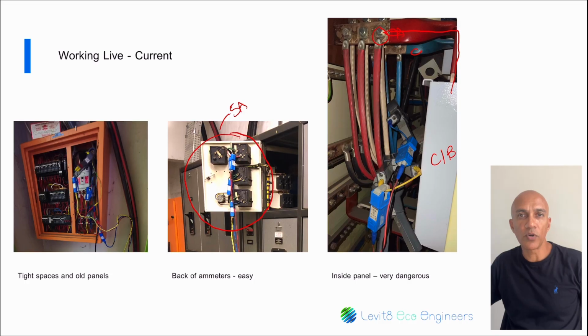If you are using a clamp-on CT that came with the instrument, it is likely that it will be rated 100 amp or 250 amp or 500 or 1000 amp. In that case, you would have to firstly ensure that the rating of the CT can handle the maximum amps of the feeder. That is, it must be rated equal to or higher than the feeder circuit breaker. Now, we discussed this in a previous section when discussing the CTs. With these type of CTs, the instrument either automatically detects the rating, or you have to select from a preset list and the instrument will display the correct amps.